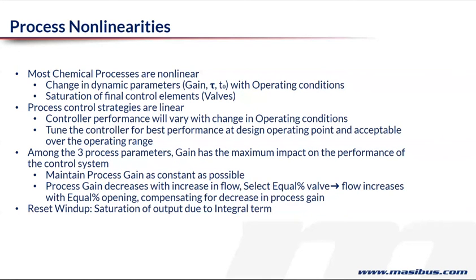So in a steam heater, depending upon the flow of the media, I'm not talking about the steam, the media which is flowing through the steam heater, whether it is water or oil or some other fluid, depending upon that flow, the gain of the process will change. The time constant will change, the dead time will change.